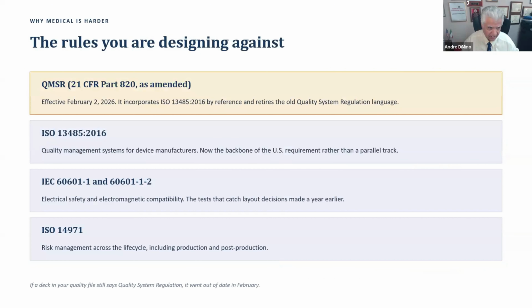Okay, let's move on. And this plays again into what Leo just said, and that is the standards that you're working with when you're designing a device. A consumer device is a lot different, because medical devices have a lot more standards. And of course, as of February 2nd, 2026, it's the QMSR and not the QSR, which incorporates ISO 13485:2016 into the FDA QMSR. Then, of course, we continue with the ISO requirements for international and now for the US as well. And Leo pointed out the testing for 60601. And of course, now the big focus is on risk management and everything related to risk.